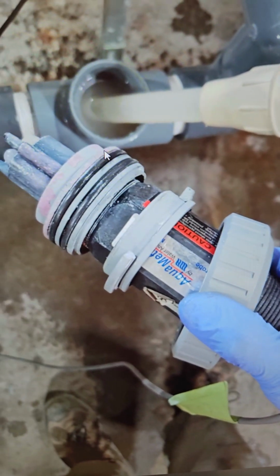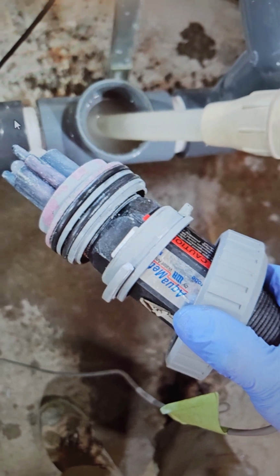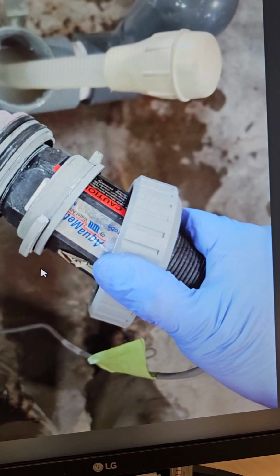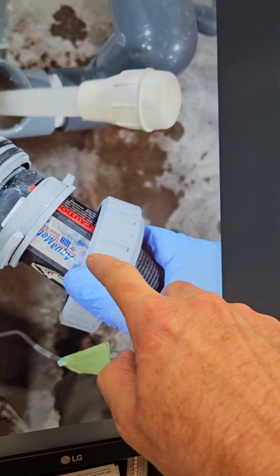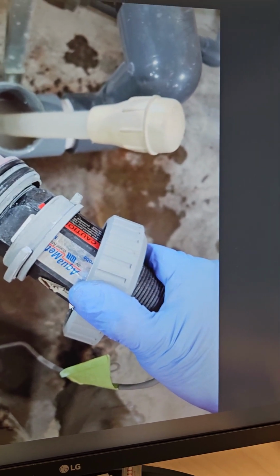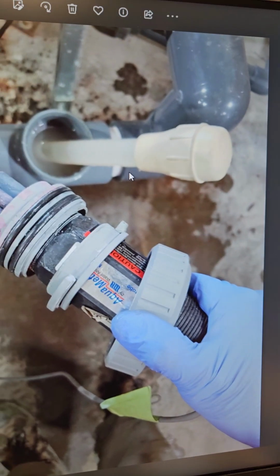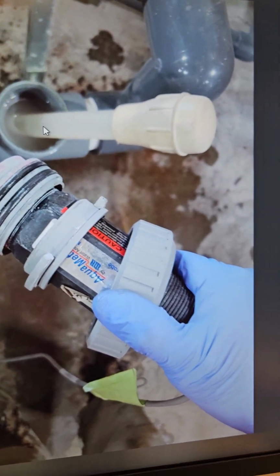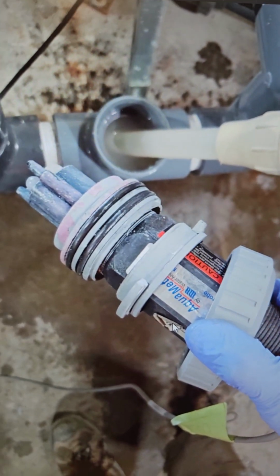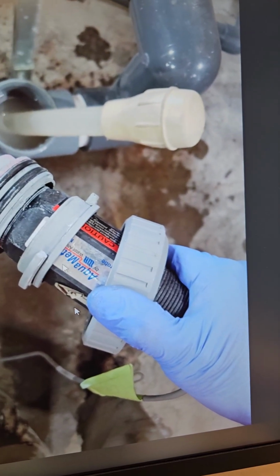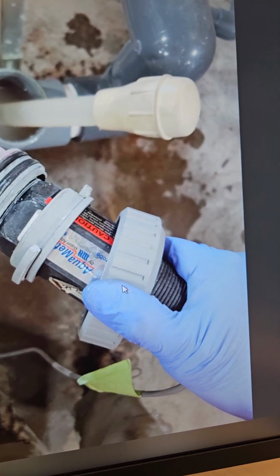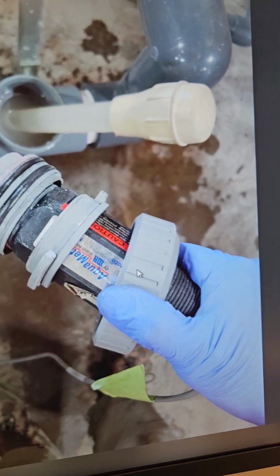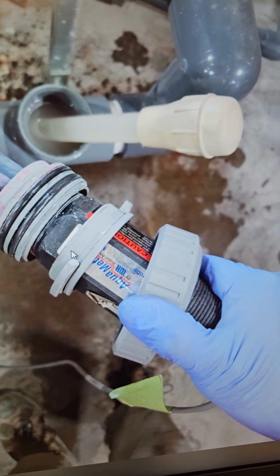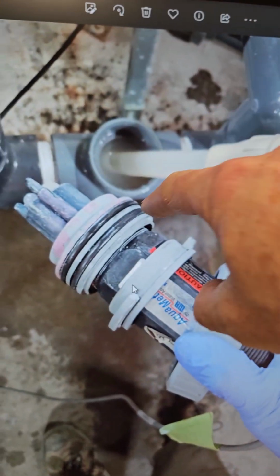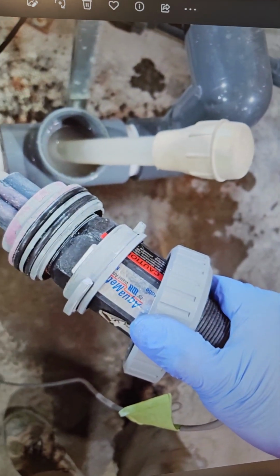Here's a problem. What happens when people don't have a drain on the bottom? They close the valves, it's completely flooded. They start torquing this nut with a large pipe wrench or something to try to pull it out of the water. And because air can't get in, water doesn't compress or expand, it just creates more and more pressure until it just pulls apart the plastic piece. That's where they destroyed the part, because this should be almost finger tight. You should be able to loosen this up and take this out. If it starts to tighten up as soon as you start turning it, that's because it's trying to pull this out of water and air isn't able to get in, and then it basically becomes the problem that people wind up having.